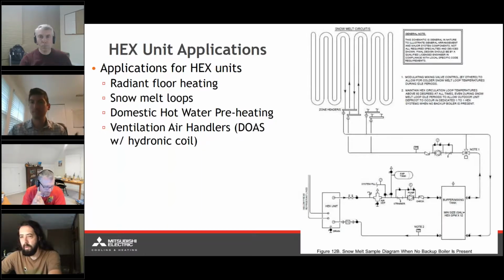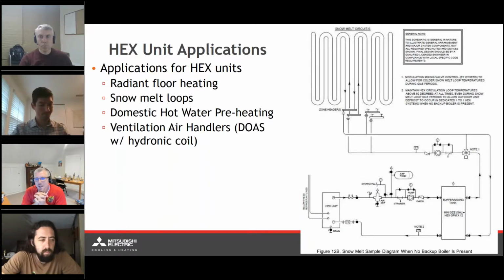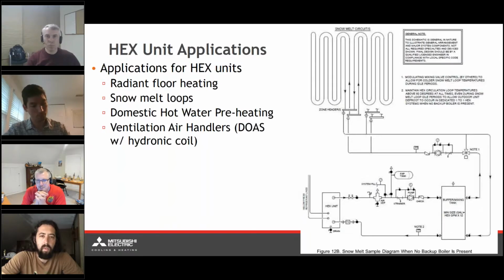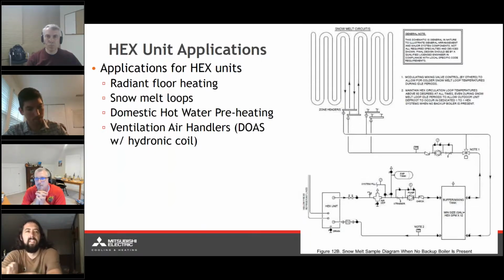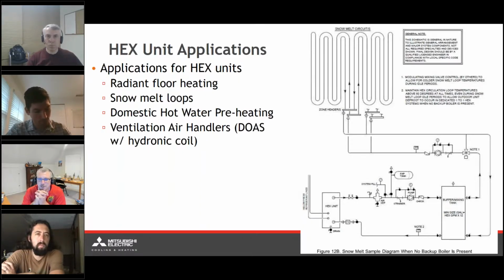I have a question about the domestic hot water, which I know you mentioned you have to research. If they're not instantaneous and they need to store domestic hot water for the system to operate, why is it that during the day we're only storing, say, half or two-thirds of the quantity of water, controlling it by the middle and upper sensor? It seems like with a system like that, you'd want to run constantly at a slow rate and keep building for 24 hours, for the capacity of the actual tanks, so that you don't run out during the 24-hour period.